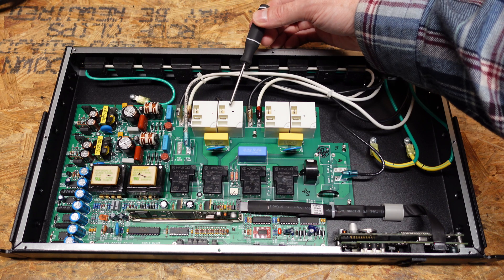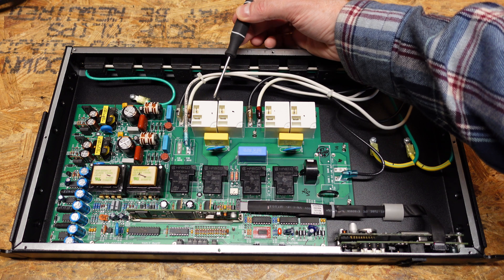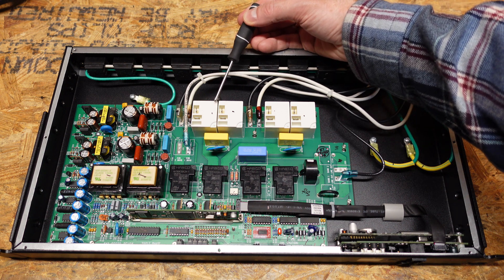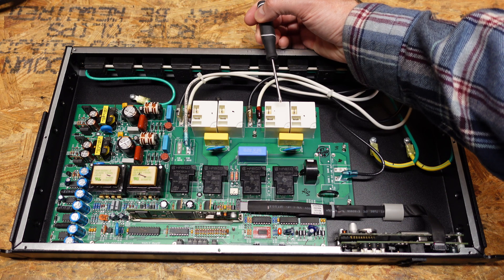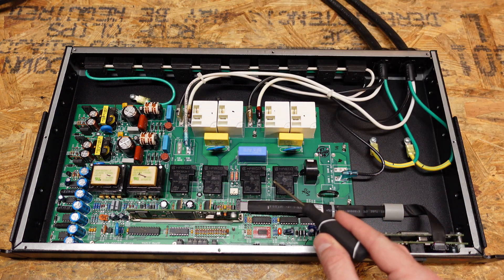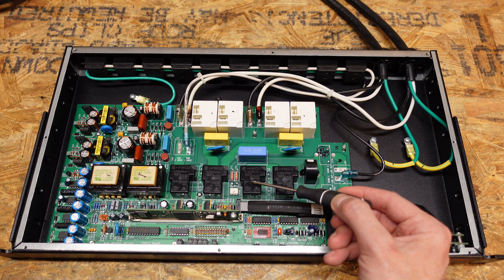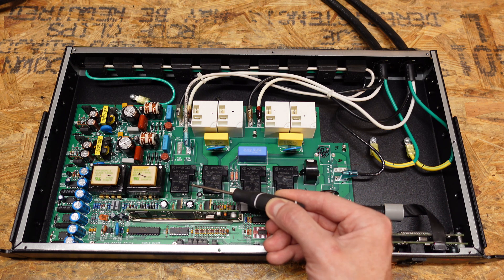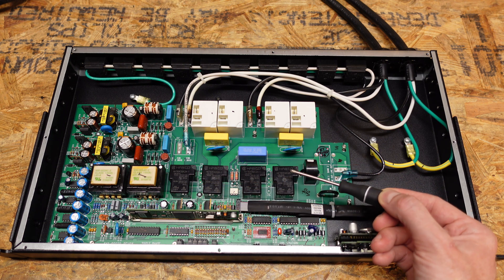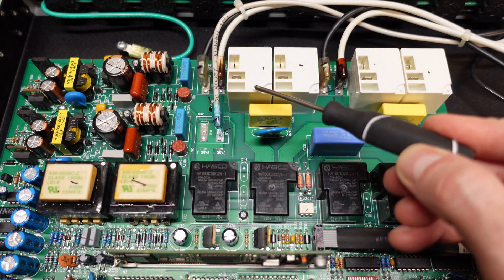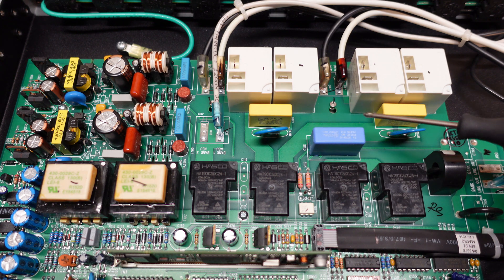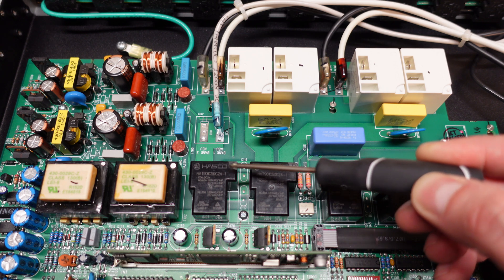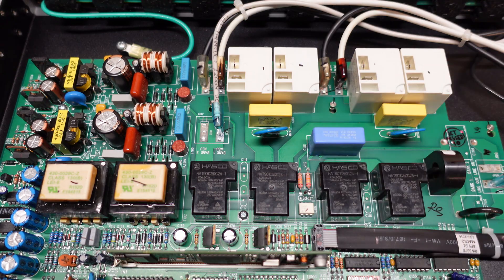Now, I believe these are isolation relays. On the side of this, it does say the coil is 120 volts. So I believe these relays will engage when the device is plugged in and then disengage when you unplug it, just to make sure that those male plugs at the end do not have power on them for safety purposes. So then we have two pairs of relays down here. I believe the first relay is switching between the two sources, and the second relay in each pair is switching the output on and off. So again, we have that isolation protection. I can see on both of the neutrals here, the large trace comes into this relay and then the large trace for the neutral comes out and goes into this relay. Then this relay passes to this relay, and then the output of this relay goes up here to the output neutral.